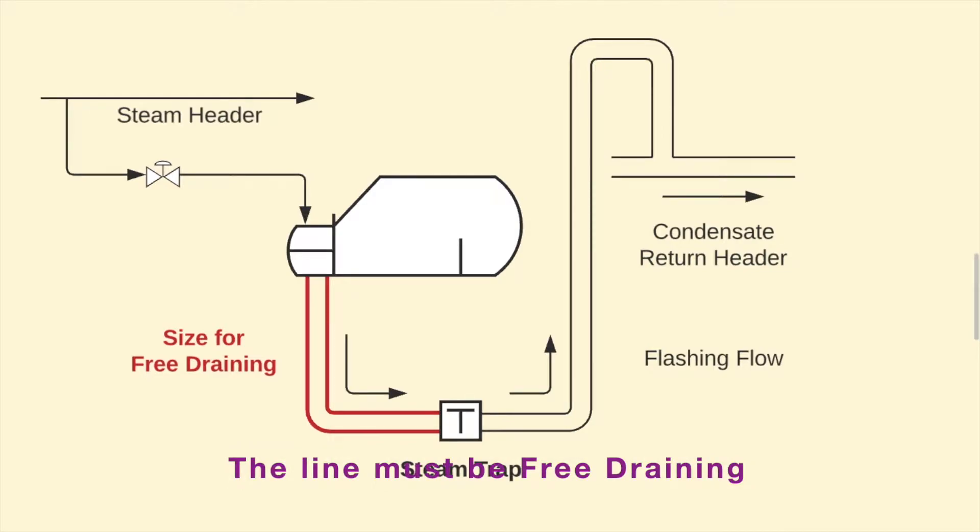The inlet line for a steam trap needs to provide two functions. It must drain water, and it must let the vapor flow back up the piping. The line needs to be free draining.